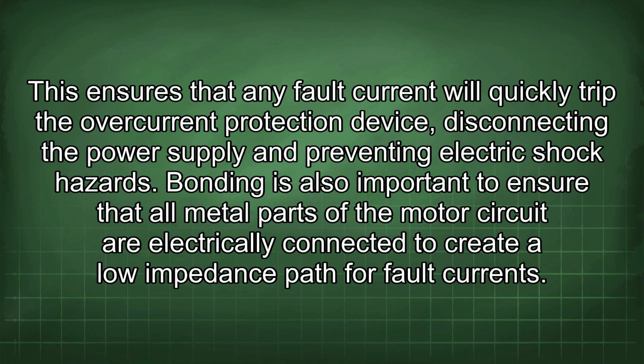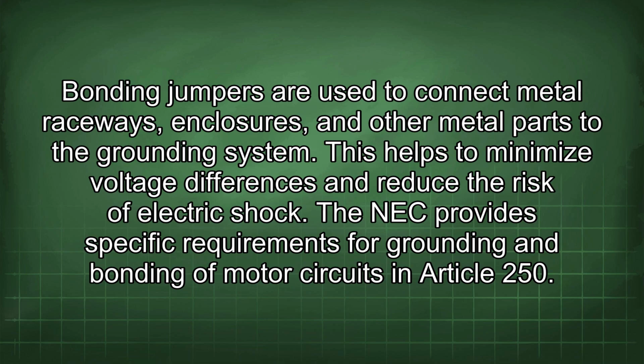shock hazards. Bonding is also important to ensure that all metal parts of the motor circuit are electrically connected to create a low impedance path for fault currents. Bonding jumpers are used to connect metal raceways, enclosures, and other metal parts to the grounding system. This helps to minimize voltage differences and reduce the risk of electric shock.